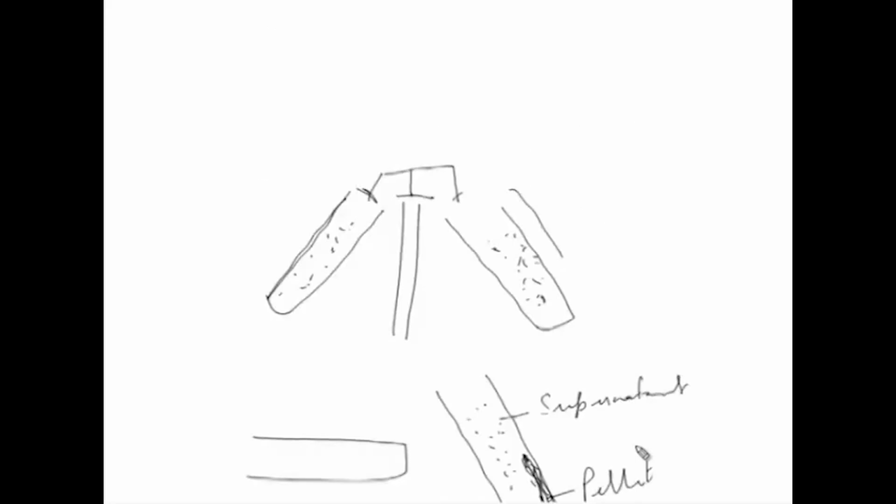In here this tube is constrained in the slot, but these are not constrained, they are open. So, they just fly open, and their pellet will be at the bottom, because the centrifugal force is in this direction. Here the centrifugal force is in this direction, therefore the pelleting will take place on this wall. Likewise, in vertical tube rotors it will happen.